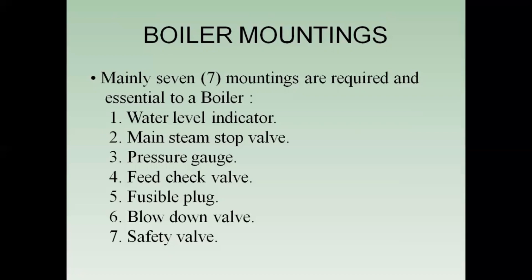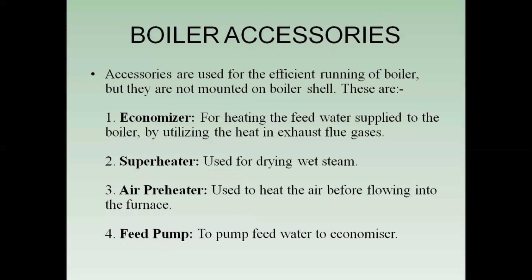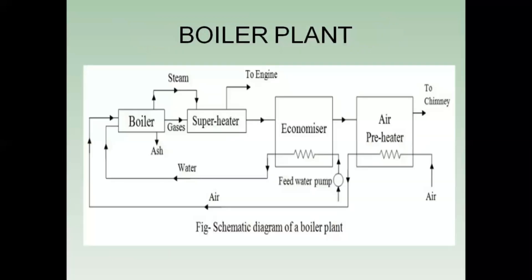Then comes the blow down valve. Then comes the safety valve — it blows off the excessive steam into the atmosphere and maintains pressure within the safe limit. Now, boiler accessories are the parts of the boiler which are used for the efficient running of the boiler, but these are not mounted on the boiler shell. Firstly, the economizer is used for heating the feed water supply to the boiler by utilizing the exhaust flue gases. The superheater is used for drying the wet steam. The air preheater is used to heat the air before flowing into the furnace. The feed pump raises the water pressure to push water into the economizer before it goes to the boiler.